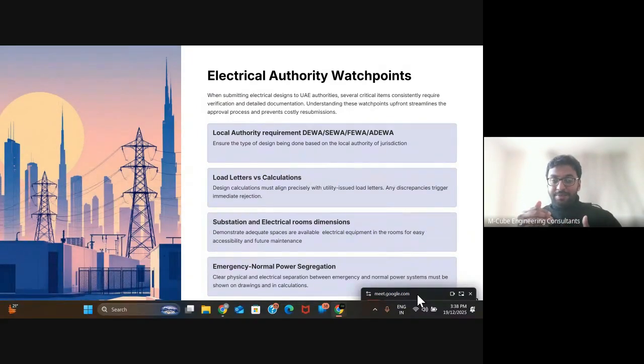Another important aspect in electrical design is room dimensions. During initial design, we estimate the load for a project. Take our example of a G+50 building: we need specific space allocated for the substation or transformer room if in Dubai. You must estimate the load needed for a G+50 tower and ensure sufficient space, not only for transformers but also an HV room, since it's a very high rise with very high load requirements.